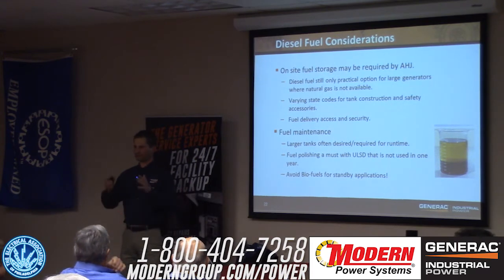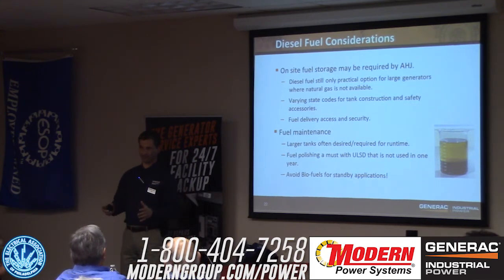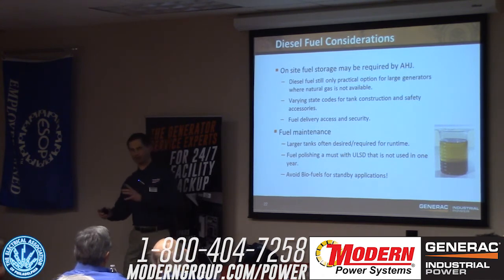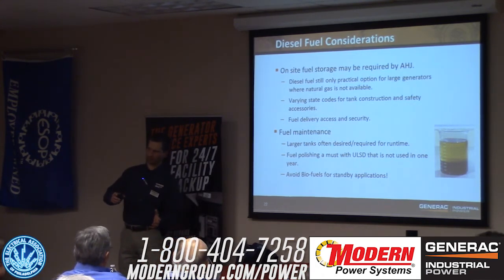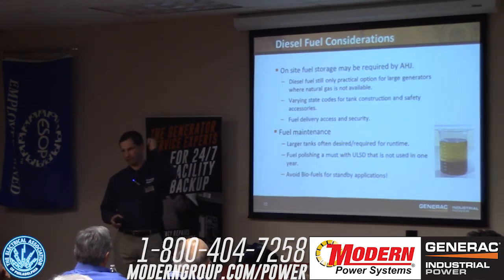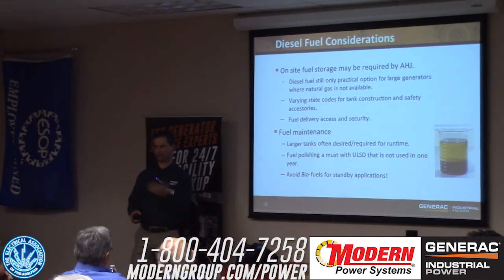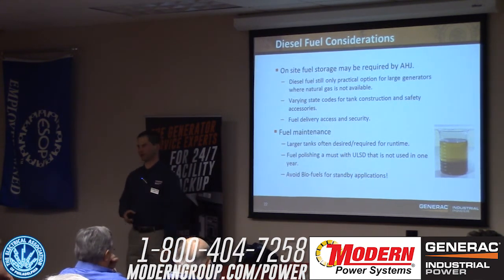Typically diesel will last about a year before you have to think about polishing it, and depending on the environment, 2 years, maybe 3 years on the outside even if you're polishing it. If you haven't used it in 3 years, pump it out and replace it, because it gets to a point that even polishing doesn't do it anymore.